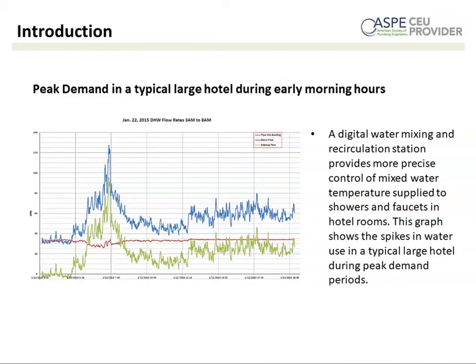Another benefit is the ability to monitor flow. Some systems can do this, some do not currently, but the ability to look at your mixed outlet flow and your return flow, calculate load flow, and on top of that calculate the energy consumption around it is certainly a nice feature and benefit. One of the great benefits of having flow meters is the ability to see whether your mixing valve is properly sized. In many cases we'll see oversizing of valves, where the belief is, obviously nobody wants to run out of hot water, that's critical, so there's a tendency sometimes to go a little bit bigger. This is particularly true of mechanical or thermostatic mixing valves. The larger you go, the more difficult it is to control at lower flows, right?